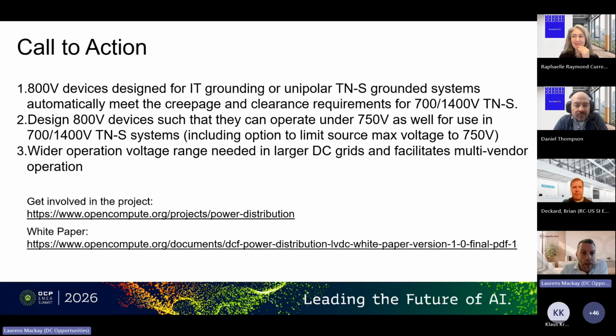So basically, you can get ready for that and design appliances right now that are ready to operate with all these systems. The important message here is that devices now being designed for 800 volts, designed for IT grounding or unipolar TNS grounded systems, automatically meet the requirements for 700/1400 volt TNS grounded systems.